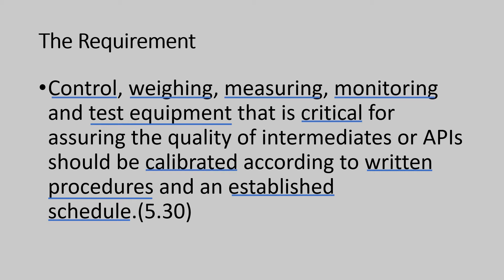Let us understand the intent of the requirement. We have all sorts of controlling, weighing, measuring, monitoring and test equipment for the manufacture of APIs and intermediates. There is a rider here — critical for assuring the quality. All the listed items have to be calibrated if critical for the quality of the output. It is recommended to have a detailed list of critical equipment. Any equipment that has direct impact on the quality of output is considered as critical. This aspect has to be established by a detailed discussion and evaluating through risk management principles.